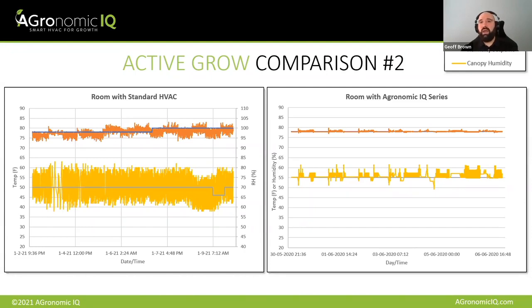So when you're banging stuff on and off, which is ultimately what's happening here. You've got a standalone dehumidifier or a packaged air conditioner that says, okay, my room's too hot, I'm going to turn on 100%, I'm going to drag the room down until I'm at my low deadband set point, I'm going to turn off, I'm going to wait for the room to heat back up and rinse, repeat. There's no modulation and control there. And so not only is your room environment not that stable, but it's also an energy pig as a result.